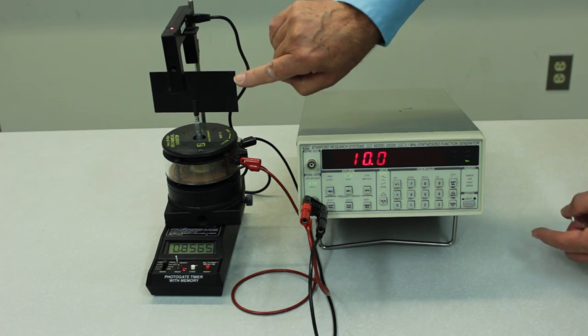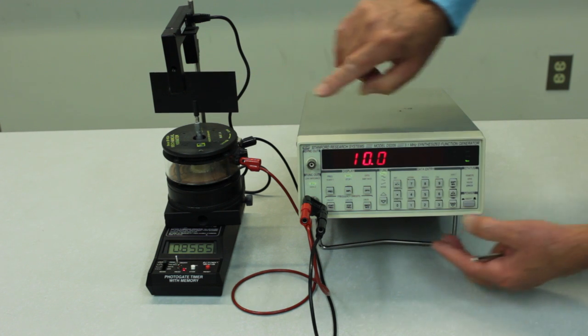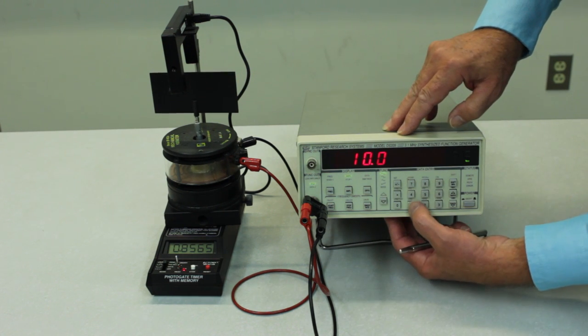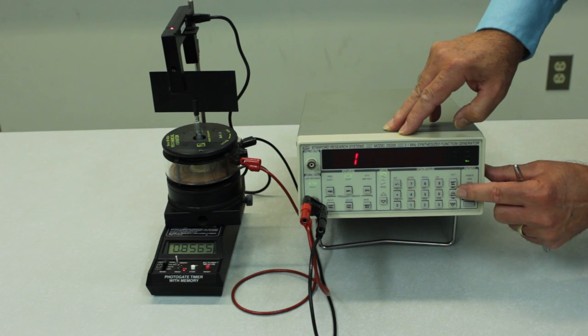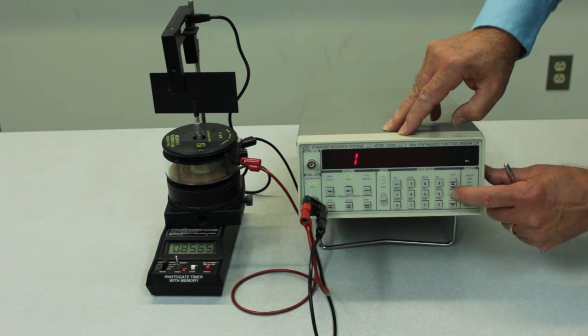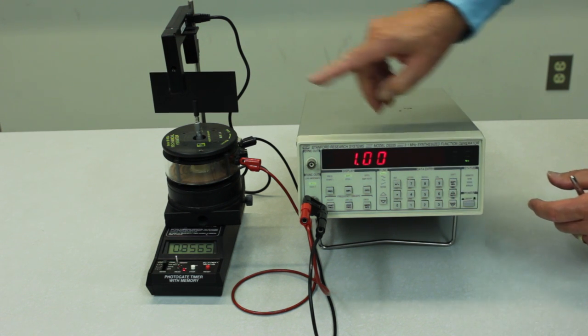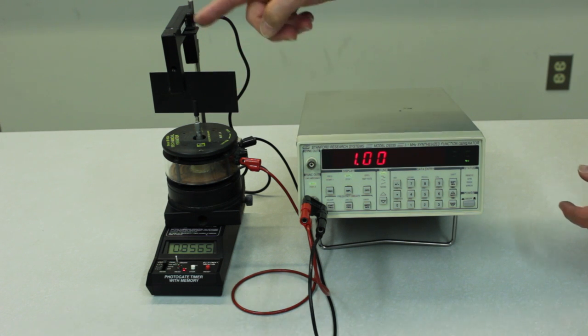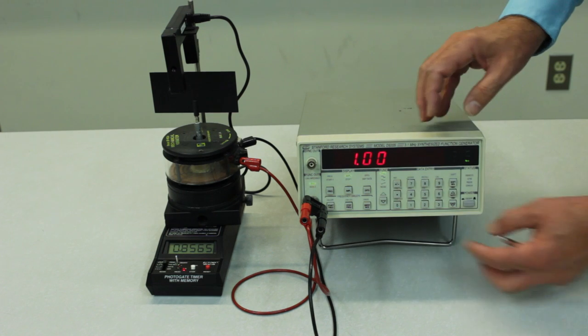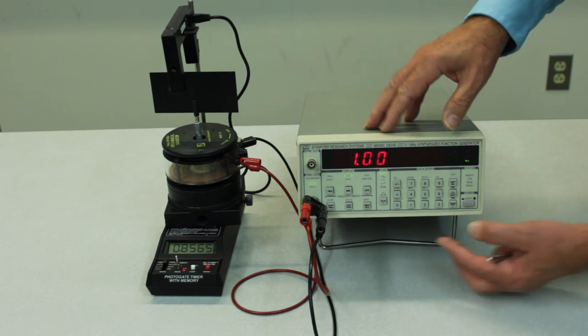And you'll just watch what happens if I don't have the amplitude set high enough. Let me set this to 1 volt peak to peak. And now the flag is not moving with enough amplitude to trigger the gate. So it's important not only to set the correct frequency but also to have sufficient amplitude.